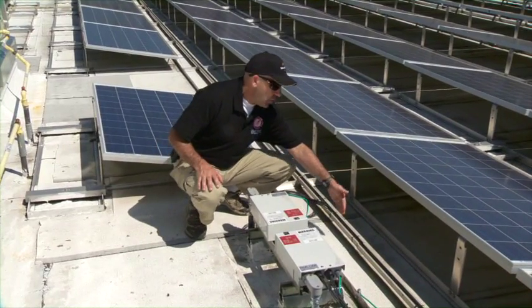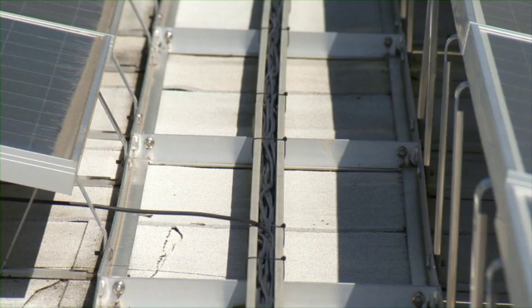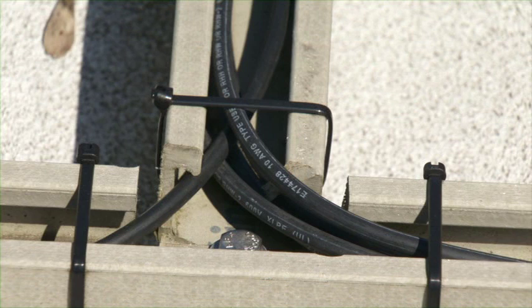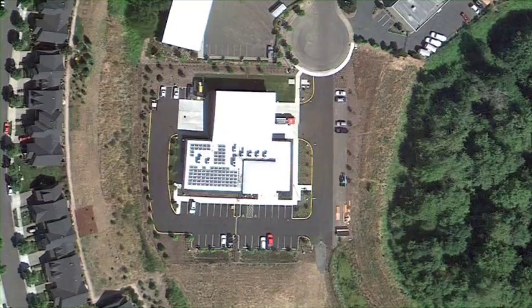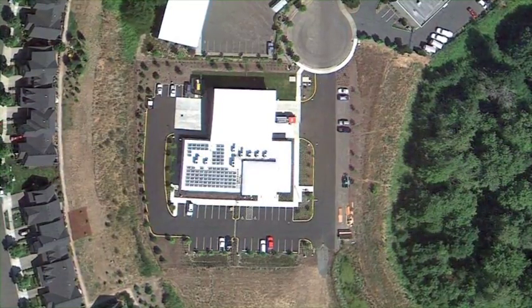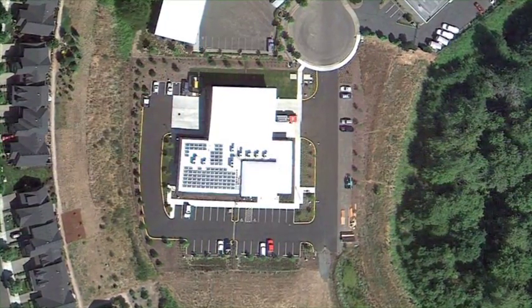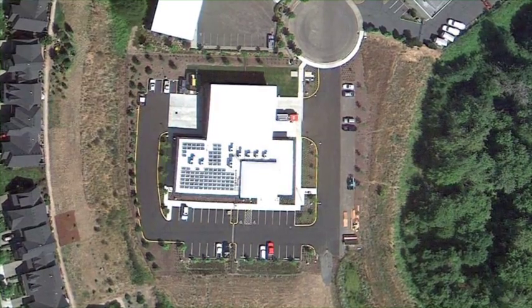We can see these raceways that all the wires are in. This is good because it's keeping it up off of the roof, but there might be some sharp edges that over time could abrade the wire. Some of the commercial fires that have occurred have been in these raceways. We'd stay away from them, direct our water, try and protect the roof as best we can, but stay away from contacting the metal components with your body.